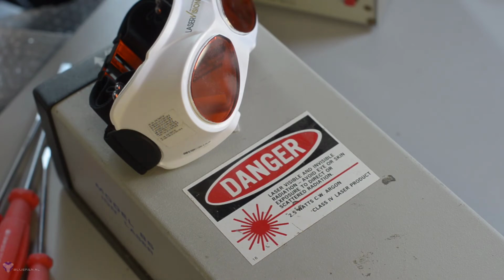The 2.5 watts power is roughly in a 1 mm square beam, and that surface area then corresponds to 2.5 megawatts per square meter. And if you look at the EN 207 laser safety standard, it should correspond to a rating of DL6, which is actually pretty high. Now fortunately I have laser safety goggles that are rated that high, but due to the fact that I have this line selector at the back, that already gives me an extra safety margin. I cannot run it multi-line and obtain a higher output power. So I would also be comfortable with laser safety goggles that are only rated for DL5.